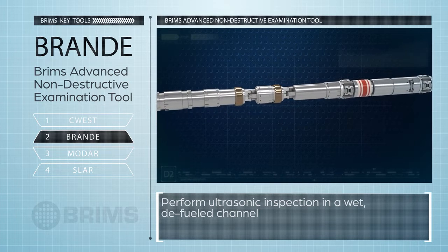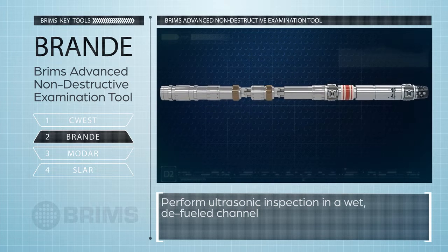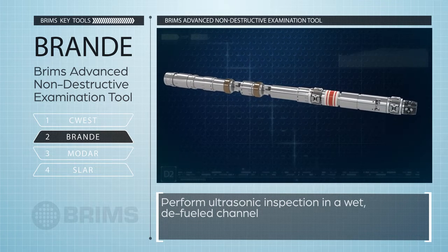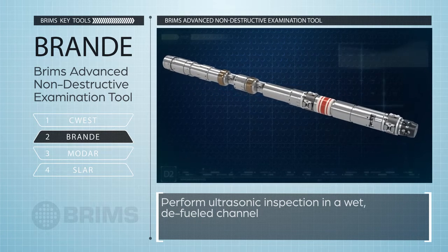BRANDE, BRIMS' advanced non-destructive examination tool, is deployed in a wet, defueled channel to perform ultrasonic inspection for flaws and to measure channel diameter, wall thickness, sag, and pressure tube to Calandria tube gap. It also locates garter springs.